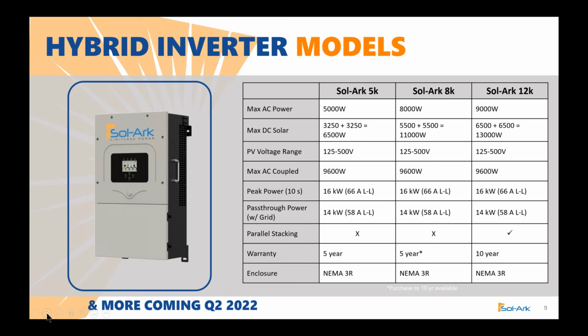The 5K and 8K are true to their name with 5 kilowatts and 8 kilowatts of AC output, while the 12K has a 9 kilowatt AC output, but we can still utilize 12 kilowatts of solar simultaneously. It's how we got the 12K name. We can do 3 kilowatts of DC charging to the battery continuously while outputting 9 kilowatts. And that's how we named our 12K inverter.